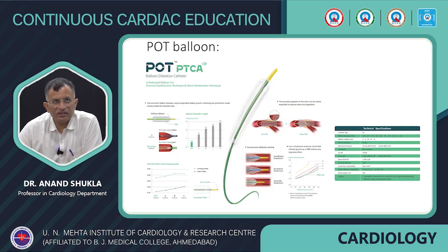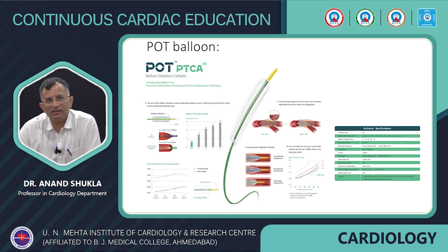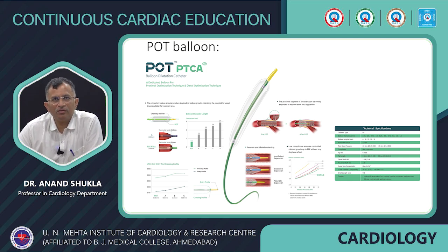The second specialized balloon category is the POT (Proximal Optimization Technique) balloon. The design difference is the shoulder — there is a small shoulder in the POT balloon less than 0.6 mm. In routine balloons, the shoulder effect can lead to edge dissection and trauma. The POT balloon minimizes shoulder length to prevent dissection. It is available in different sizes, and the POT balloon is also now available in India.